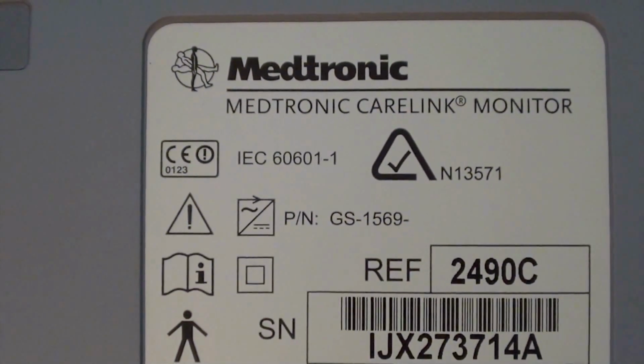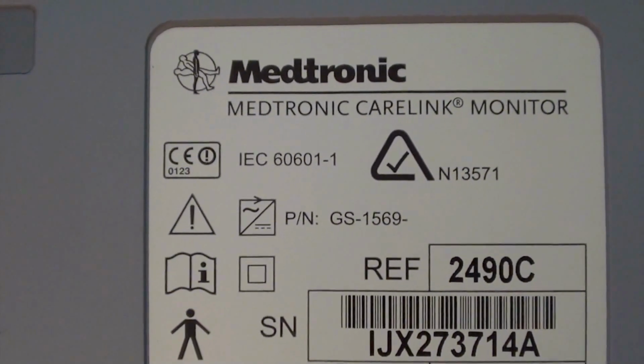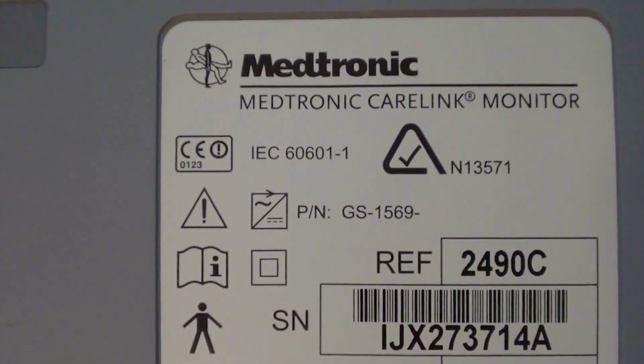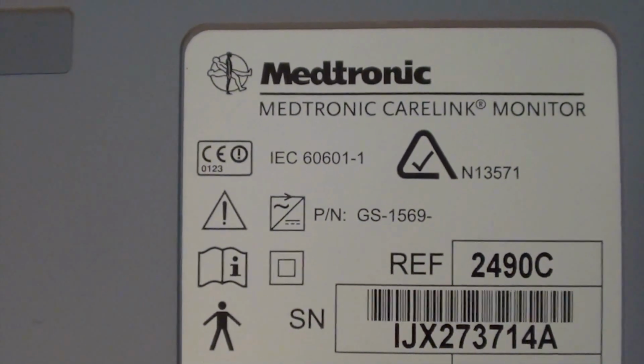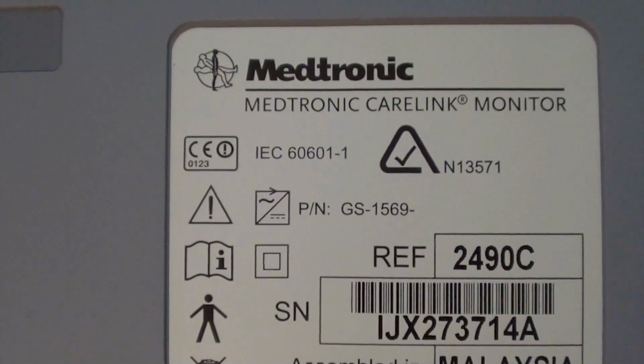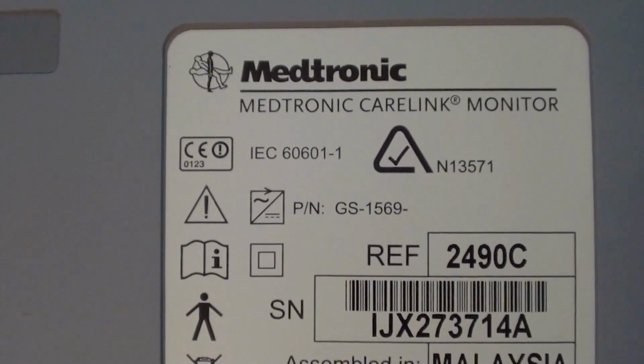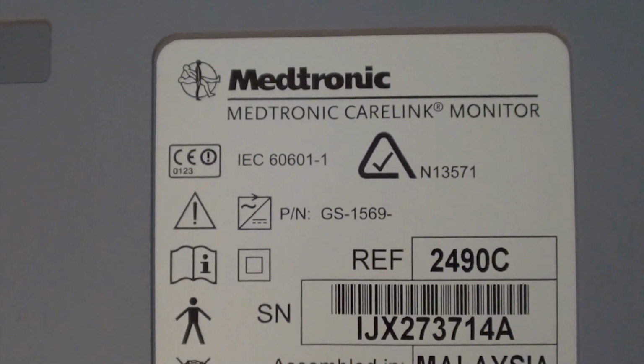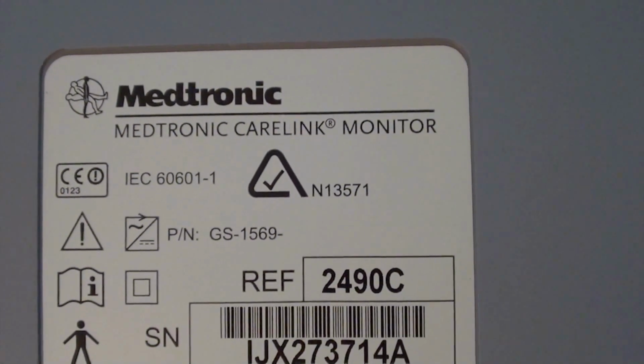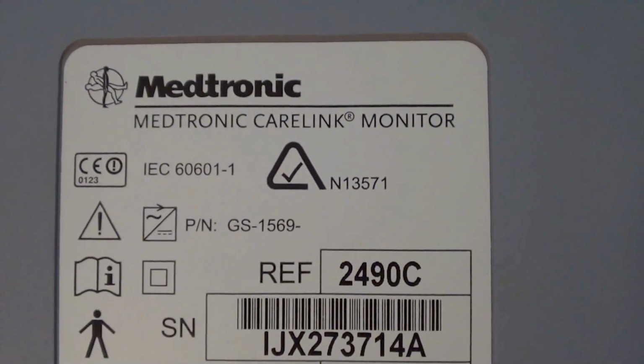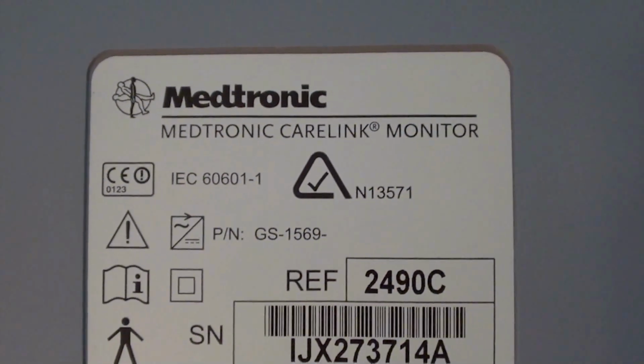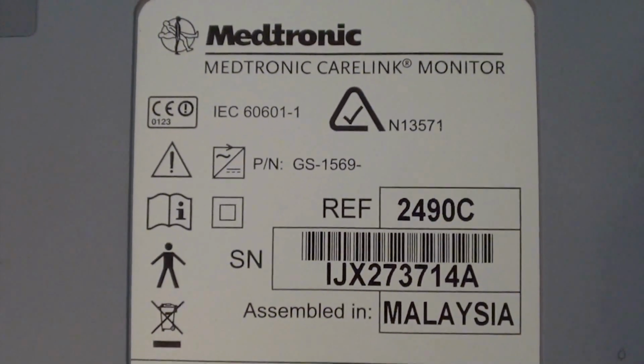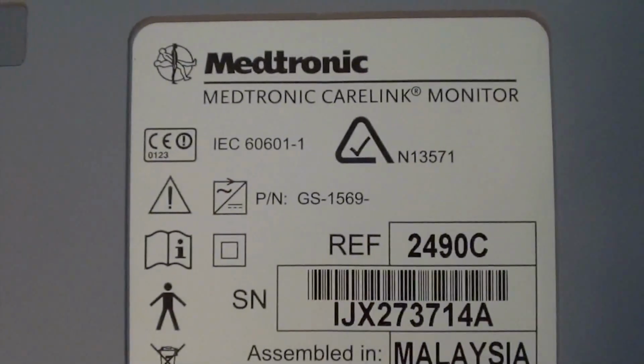Next to that we've got the IEC 60601-1. Again, this is a medical document related to devices designed to be used on patients in hospitals, and basically anything medical has to comply with these regulations. And next to that we've got another N13571, which is more classification and regulation you need to design medical devices. Below that we've got the part number.